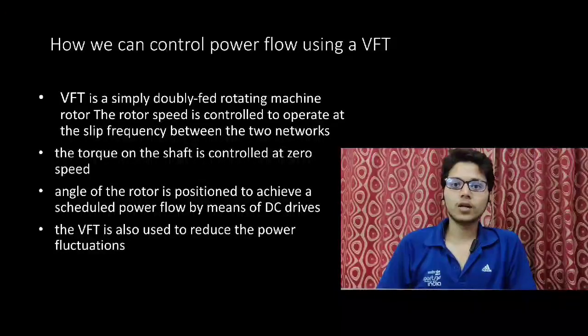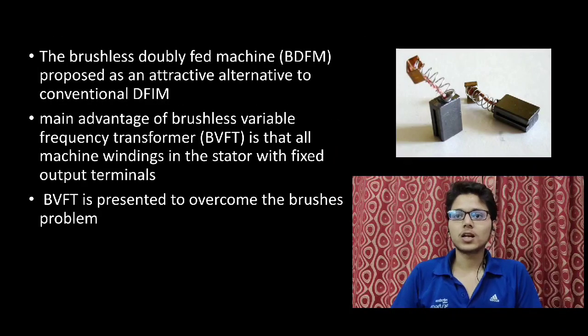Being an effective means to control power flow in weak interconnections, the VFT is also used to reduce power fluctuations of large-scale grids connected to offshore wind farms. A doubly fed machine with nested cage rotor provides advantages that may warrant its application despite an apparent power density penalty. It was proposed as an alternative to conventional DFIM in many applications, especially in variable frequency, variable speed drives for large induction machines, wind applications, and contactless power delivery systems.